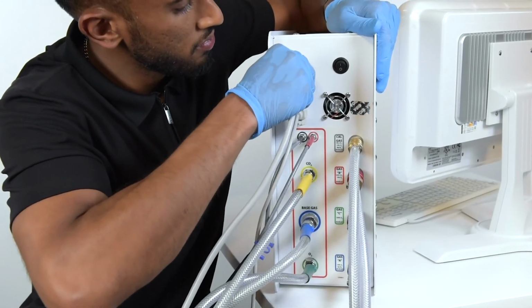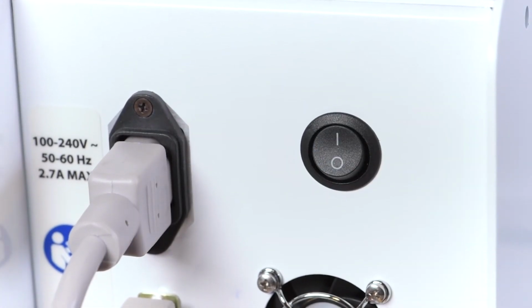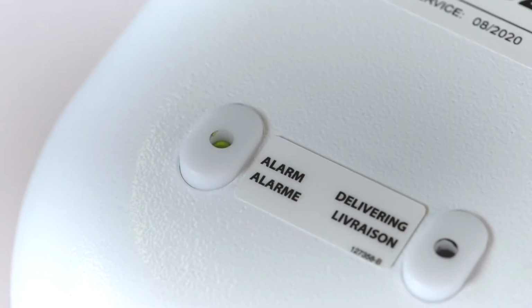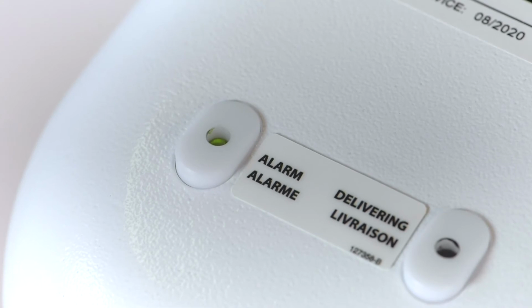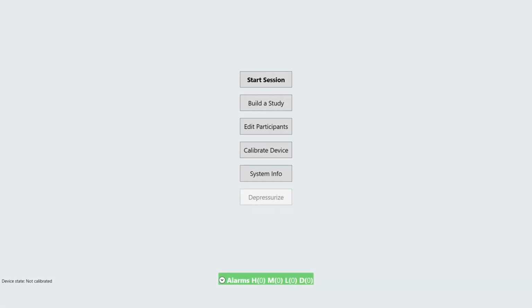Connect the power cables to the back of the control room unit and press the power button on the back of the system to turn it on. You should now notice that you do not have a red blinking communication error on the MRI unit, and the same should be reflected on the control room unit's error status LED.